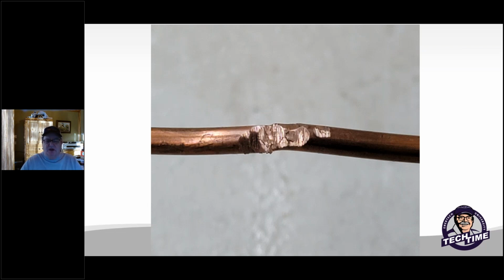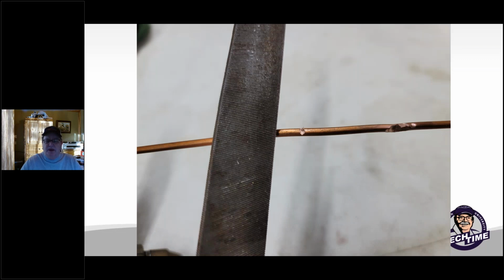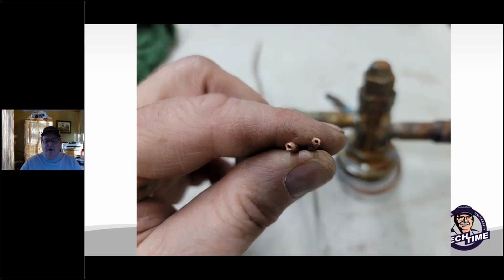You can't solder this one together because you're going to probably plug up the hole. So it's always recommended with a cap tube to use a file and make a notch in it. Don't go all the way through, but make a notch. This is how I was taught and used in my career. Make a little notch, bend it back, and you'll see they'll break apart and there are still open holes in there. So you know that you haven't plugged it all up. That's why you want to make sure that both ends are open, you don't have any little burrs in there, and that it's clean.